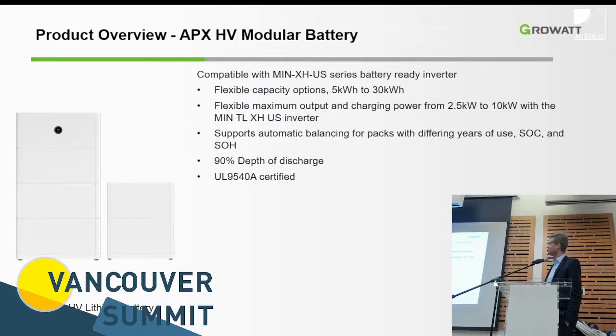As I mentioned, each increment has 5 kilowatt hours and goes all the way to 30. The system is UL 9540 certified up to 1 stack of 30. Typically, as you saw earlier, the code talks about 20 kilowatt hour increments, or if it's certified, tested and documented by the manufacturer, it can be up to 40 kilowatt hours in a residential dwelling or 80 kilowatt hours total. In this case, the fire propagation testing was done in 1 increment up to 30. So you can have 1 stack without any spacing requirements to a second stack, for example, as long as you stay below the 40 or the 80 for separated.